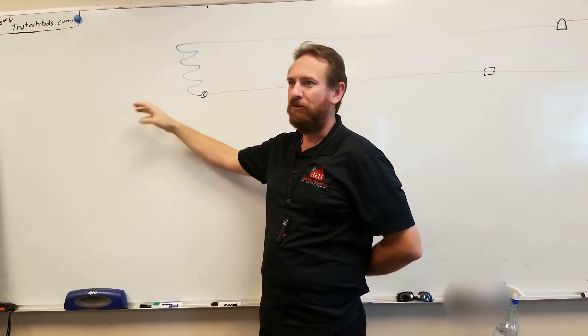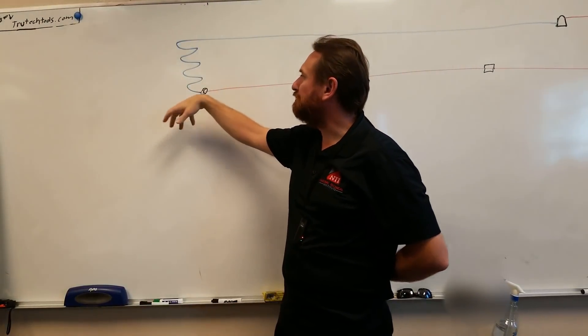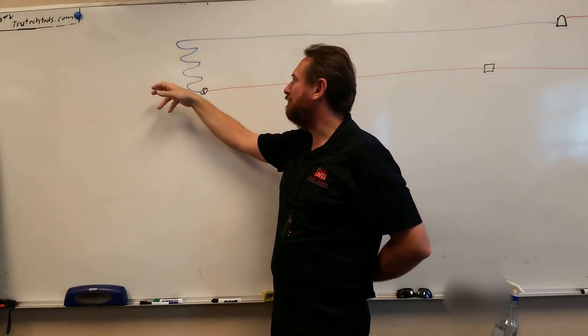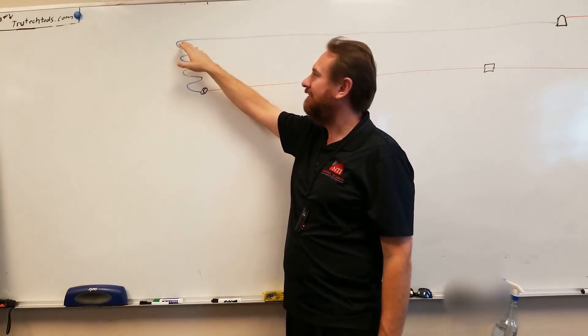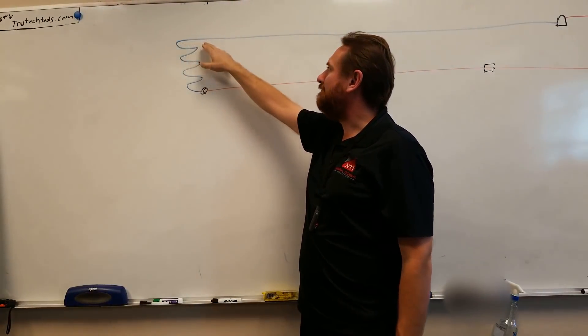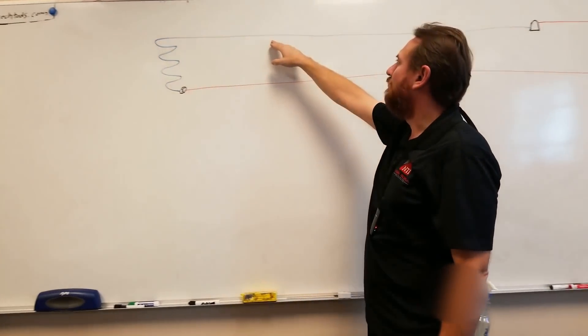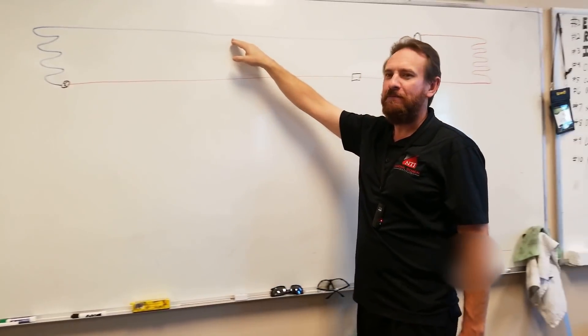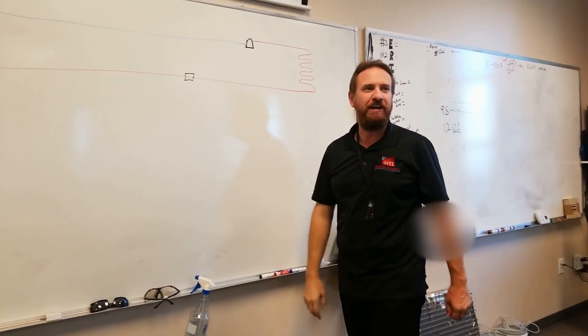So we absorb heat from the air into the lower temperature refrigerant. The refrigerant boils from a liquid to a vapor — the heat is hidden, it's latent heat. Then after that we superheat that vapor, and we have a superheated vapor going all the way back to the compressor.